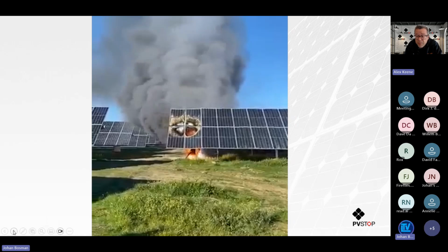What you're seeing here is a combiner box failure. This is where the strings are combined in the cabling sense to create a parallel circuit. When there's a fault within the combiner box, whether that's exposed above ground or underground, it's a significant challenge to be able to stop that. You can also see the smoke generated, the toxic gases being generated from the burning panels, and the combustion element present serious breathing risks and challenges around that as well.